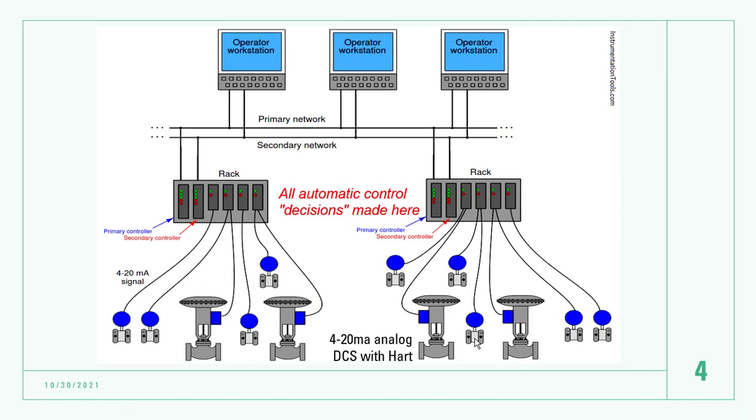The traditional DCS makes all decisions in the controller. It's a remote controller that makes decisions here. It is a primary controller and a secondary controller. For example, this one is an analog DCS with HART, 4 to 20 mA signal. Here the transmitter sends the signal to the controller. The controller has an analog input module. Then it makes decisions in the controller, PID control.